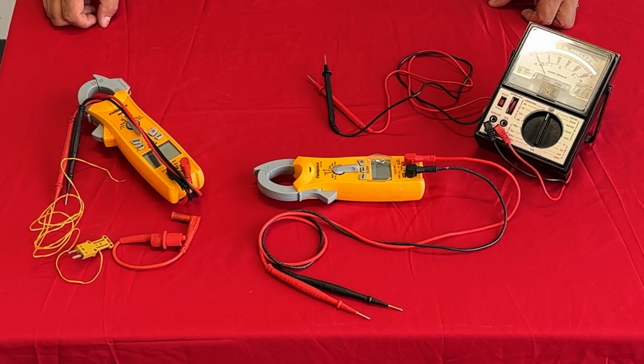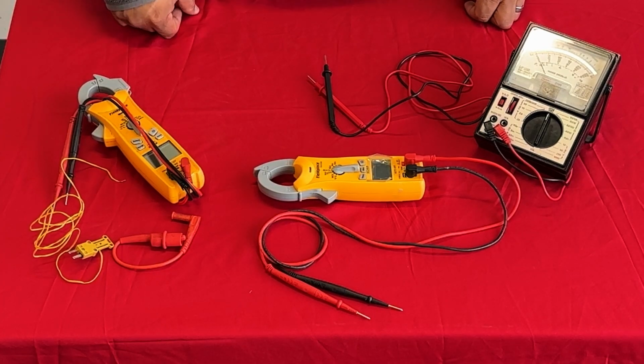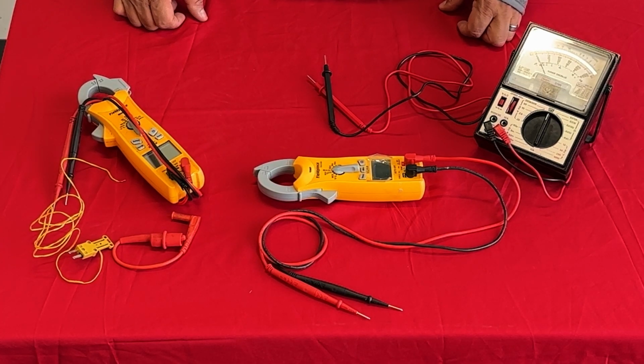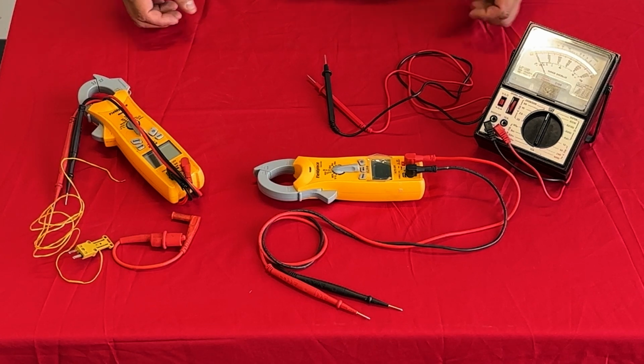The third tool we'll be looking at is the multimeter. We use multimeters mainly to check voltage, incoming voltage or voltage within a unit. We can also use them to check amp draw, and if you have a multimeter that has the option of checking temperature, you can also have a temperature probe to check temperatures. I always make sure to have a multimeter on hand whenever diagnosing a unit. The main reason is you always want to make sure that you're checking voltage, your current, double checking on any kind of contactor or relay to make sure it's not stuck open or closed.